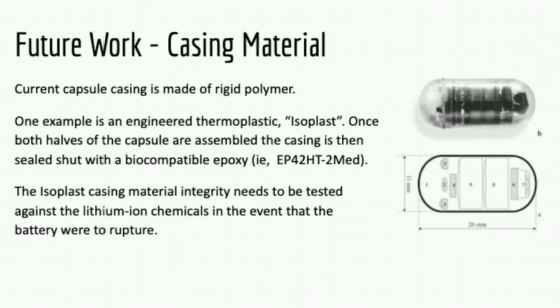Due to the supplementation of the silver oxide battery with the lithium-ion microbattery, there is an increased risk of patient toxicity in the event that the battery were to rupture. The current capsule casing is made out of a rigid polymer, which is sealed shut with a biocompatible epoxy. One key area of future work would be to test the lithium-ion battery chemicals against the integrity of the current Isoplast casing and to determine the effects. A leak-proof casing design is a huge area for future examination, and an alternative biocompatible casing material may need to be examined for future use.